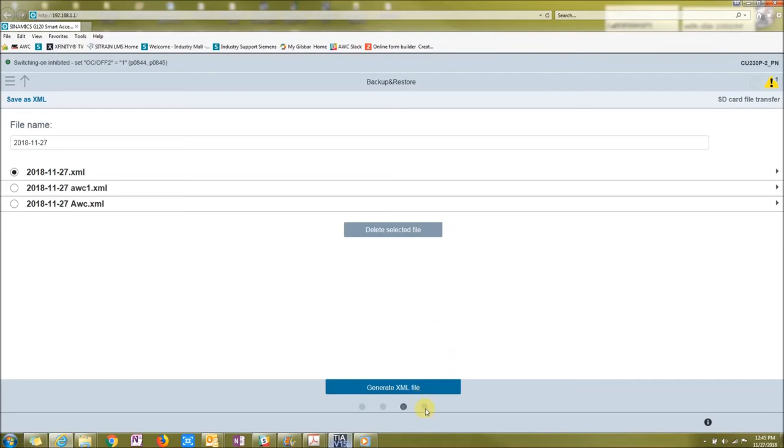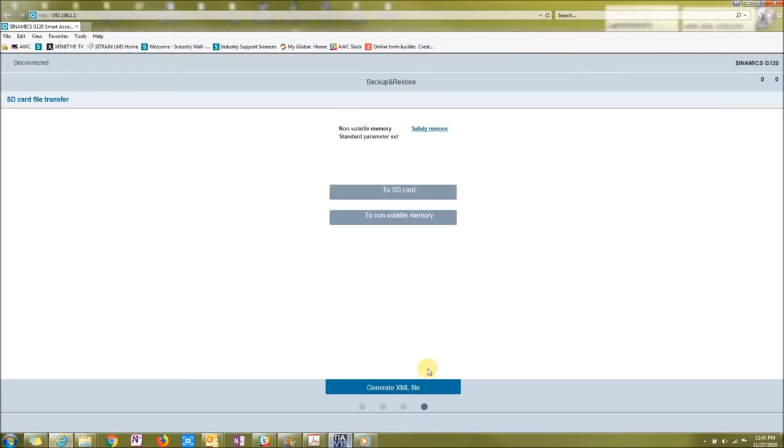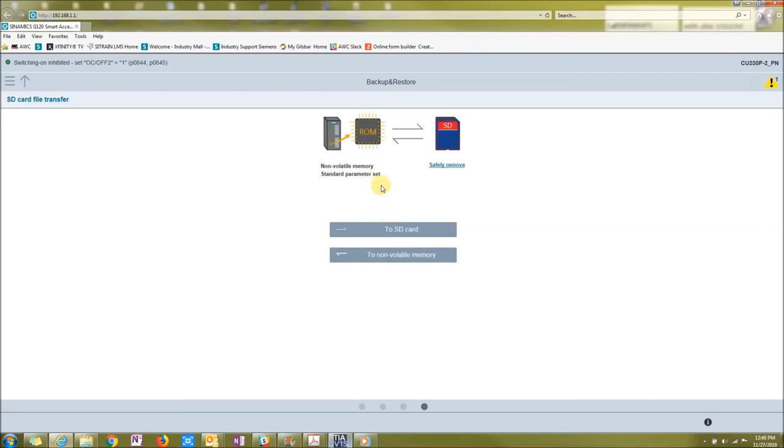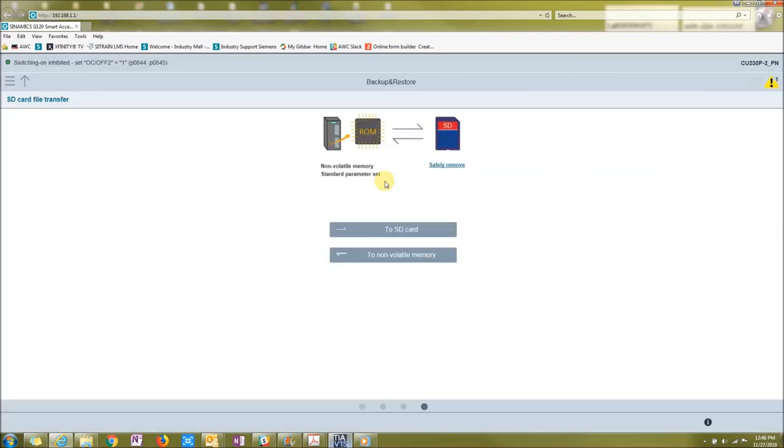The fourth dot, it lets you save the ROM memory to an SD card. Right now I'm going to plug in a SD card. And then I can now save the ROM memory to the SD card. Then you can save up to 100 files, one to 100. So if I choose it to save from one onto the SD card, I just have to write that down that this was a configuration that I want for this drive.